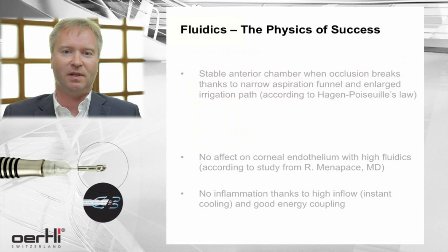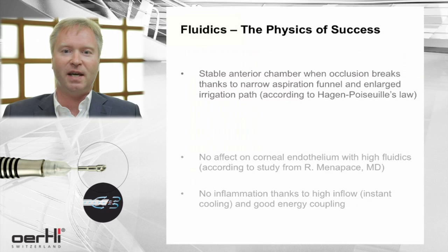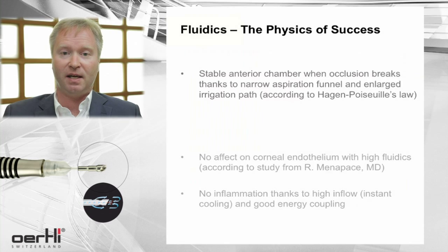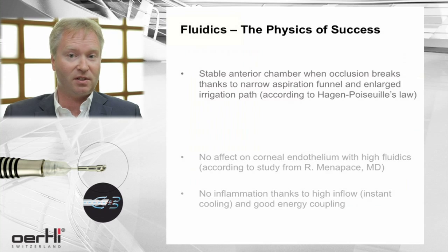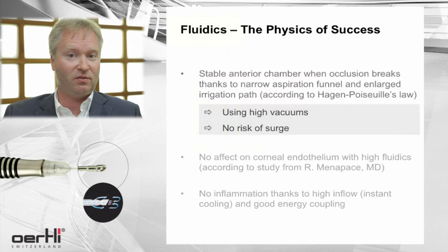High fluidics can be applied safely because of the laws of physics. Hagen-Poiseuille's law shows that if you create a narrower aspiration funnel, you are not at risk of surge if the occlusion breaks. On the other hand, active aspiration is not affected by the narrow aspiration funnel. So this gives you two advantages: you can apply high vacuum rates and you have the safety of not being at risk of surge.